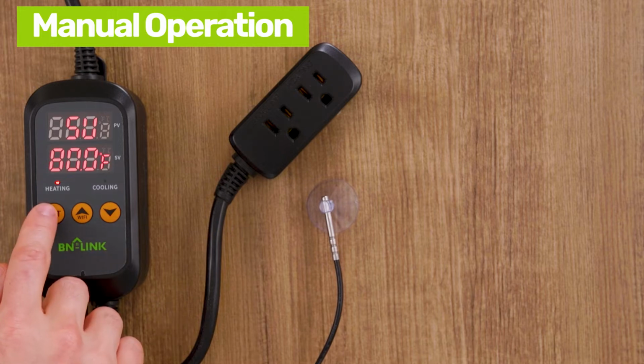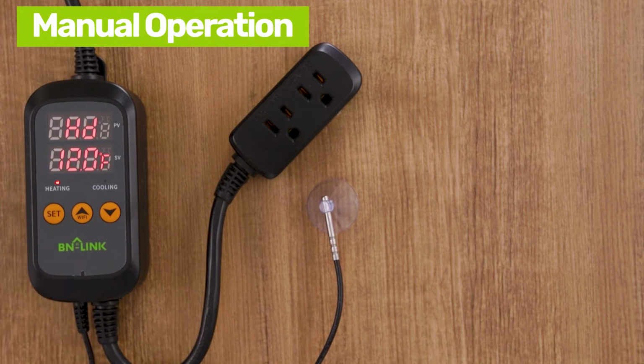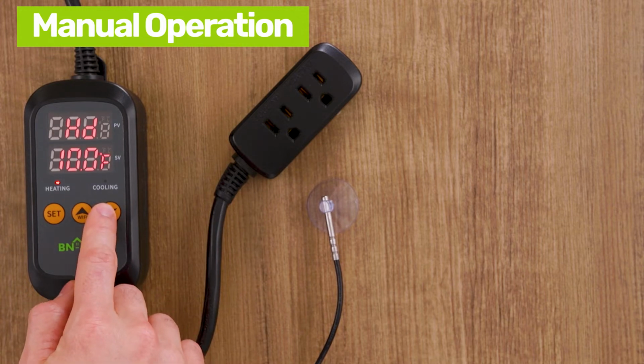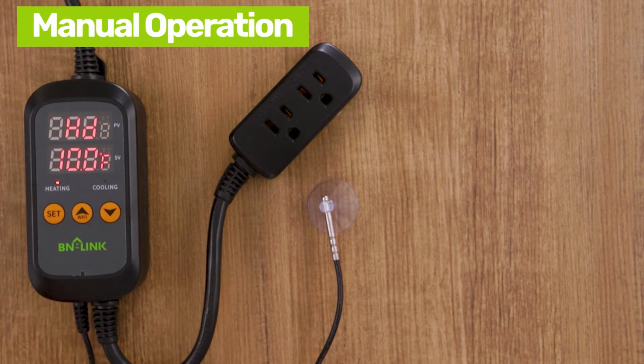Next, press the Set button again to get the heating differential value, shown as HD. Setting this will let the device know when to turn on the heating equipment. Use the up and down buttons to set the number to get your lowest temperature from the middle temperature. In our example, that temperature was 70 degrees. Since our middle temperature was 80 degrees, our heating differential value is 10 degrees. Using the up and down buttons, we will set the number to 10, since the difference between 80 degrees and 70 degrees is 10 degrees.